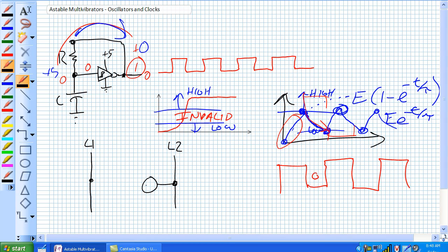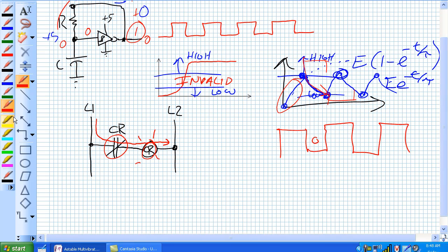And for this coil CR to energize, we need to connect line one to line two. Okay, so what we do is we put a switch there, a contactor, but it's a normally closed. So that switch, though, is controlled by this coil. So what happens is normally closed, it goes through, energizes the coil.